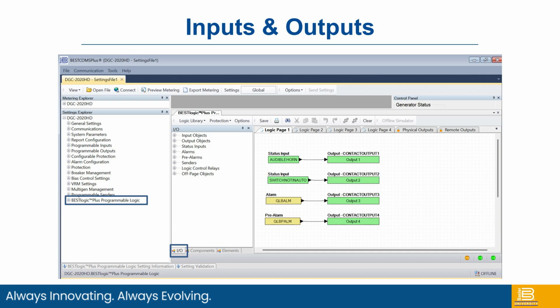Inputs and outputs, pretty self-explanatory, but basically you have an input in the middle that drives an output, and you can drive that output to a physical output or a virtual output. We have both physical inputs and virtual switch inputs, which can be configured, which is nice. If for some reason you want to do something during commissioning or testing or even troubleshooting through the BestCom software, once connected and in live mode, in that metering screen, you can open up a virtual input and trigger an output just through the software tool.